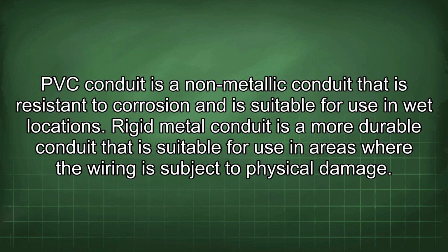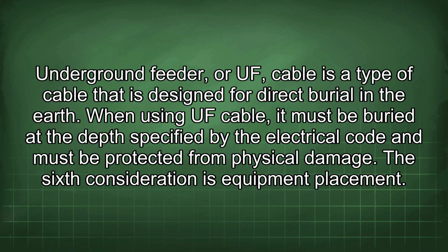PVC conduit is a non-metallic conduit that is resistant to corrosion and is suitable for use in wet locations. Rigid metal conduit is a more durable conduit that is suitable for use in areas where the wiring is subject to physical damage. Underground feeder, or UF, cable is a type of cable that is designed for direct burial in the earth. When using UF cable, it must be buried at the depth specified by the electrical code and must be protected from physical damage.